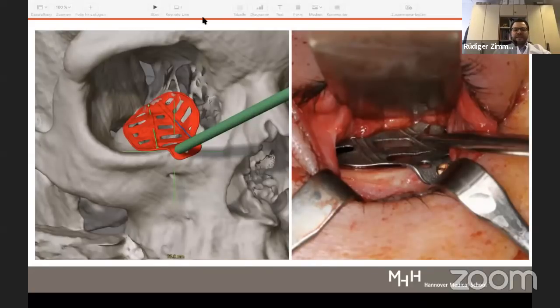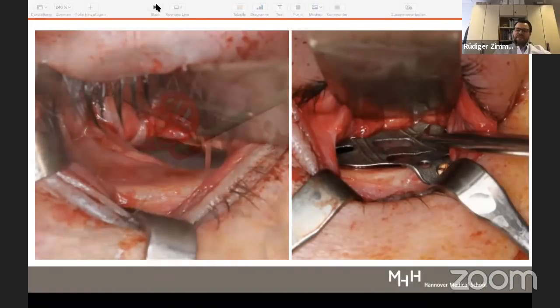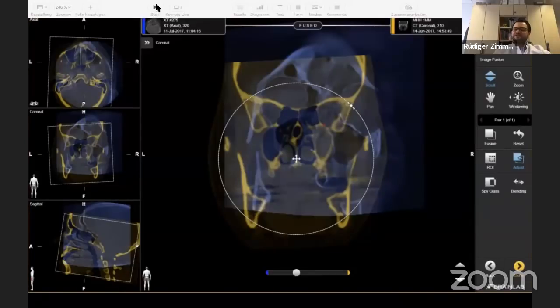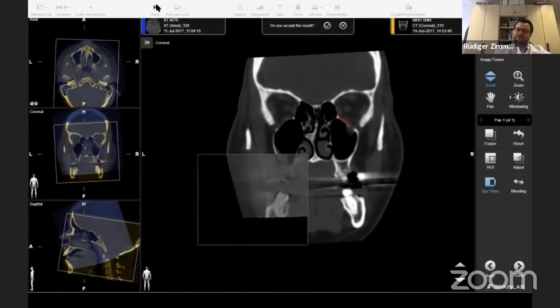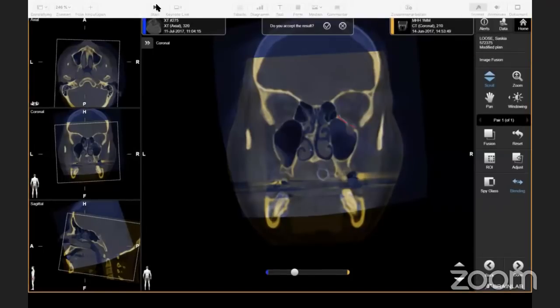And you can see the edge of the implant, it's made a little bit thicker. And this is what we call the preventive design. So you don't harm any soft tissues. There are no sharp edges here. And in the back, we do this inverted snow shovel so that the implant will never go up in the back and harm the optic nerve or soft tissues. And this is, again, what I said is called the preventive design. So this is not just an implant, this is more than a plate. This has functions like prevention of soft tissue damage and helping you put it in a perfect position.